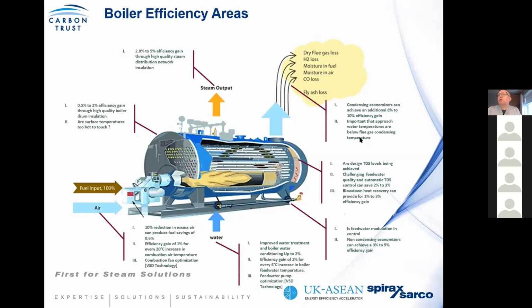And simple things like the boiler insulation itself. You could find that your boiler was installed maybe 20 years ago, and although it came with insulation around the drum, what we have found is that boiler drum insulation sags under its own weight over time. Although it was designed 20 years ago to give good insulation properties, you may find now that your boiler house has become very warm. It's stuffy, a hot environment. A simple indicator is that the surface is too hot to touch. Now, I'm not advocating that you go around and start touching everything, but do you feel heat from your boiler surface? Use a heat gun, for example, to give an indication of the surface temperature.